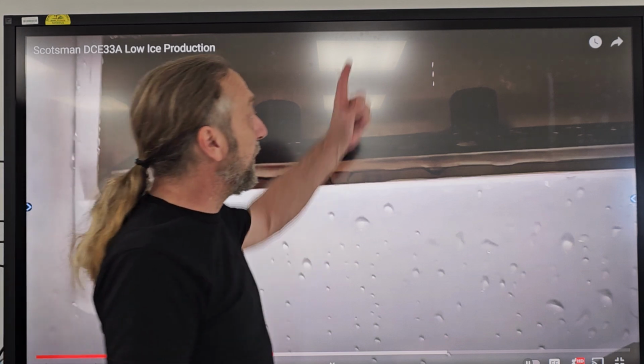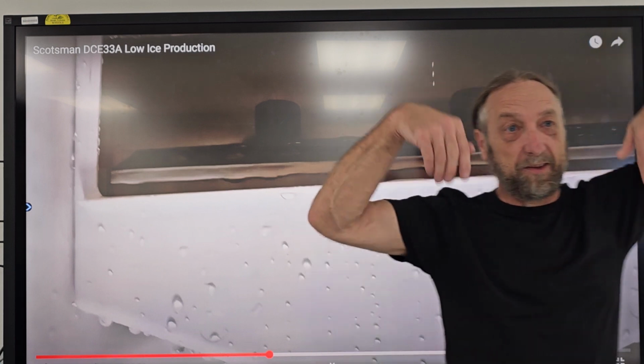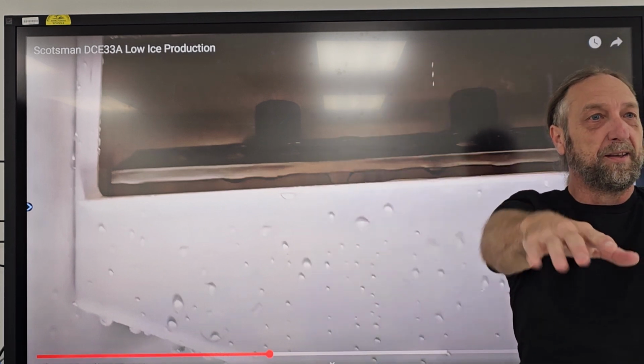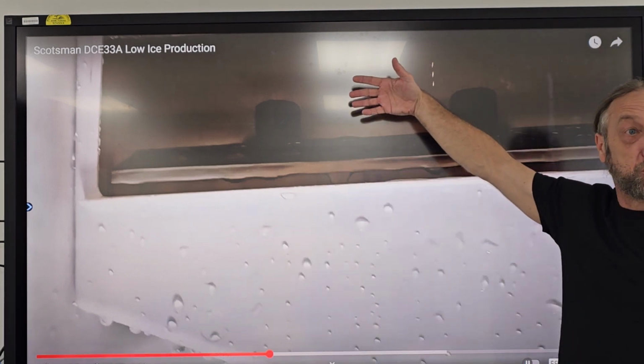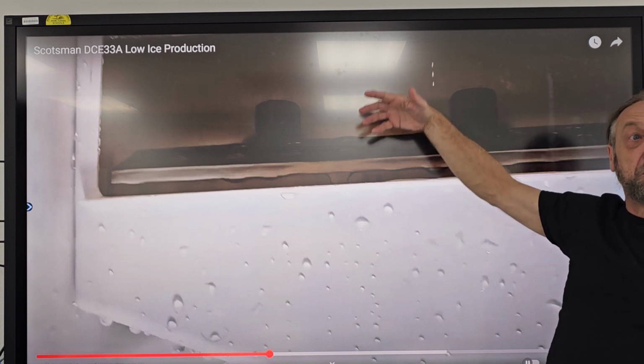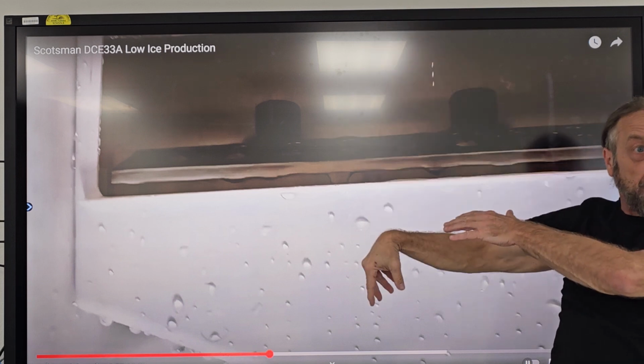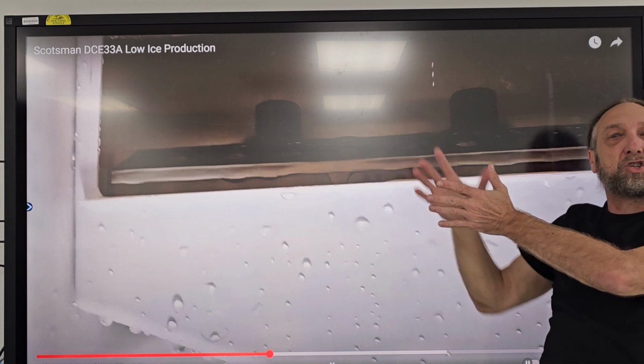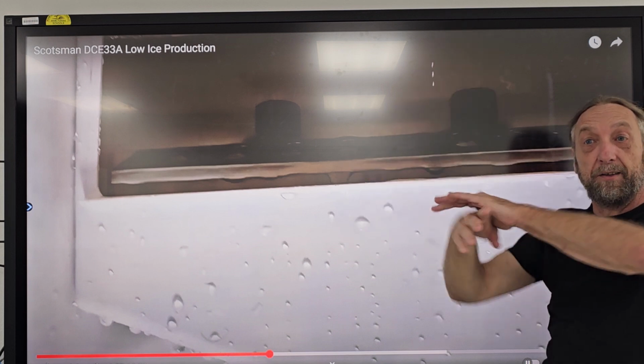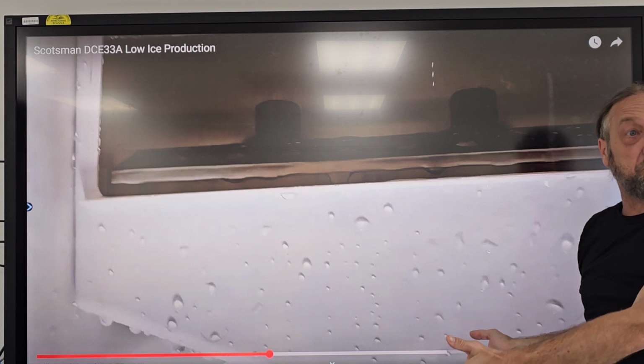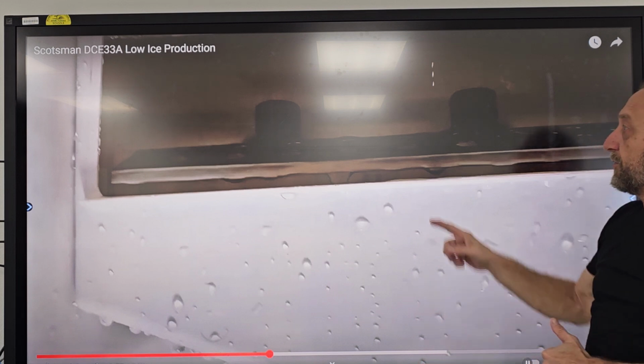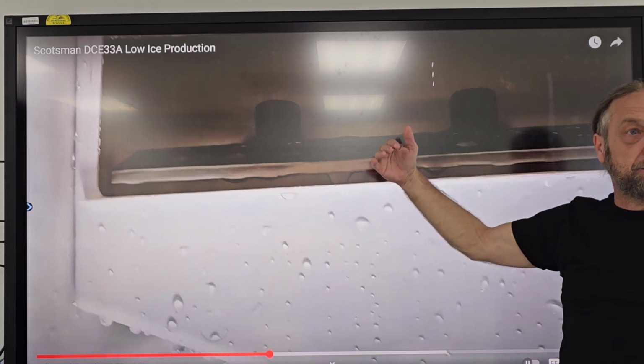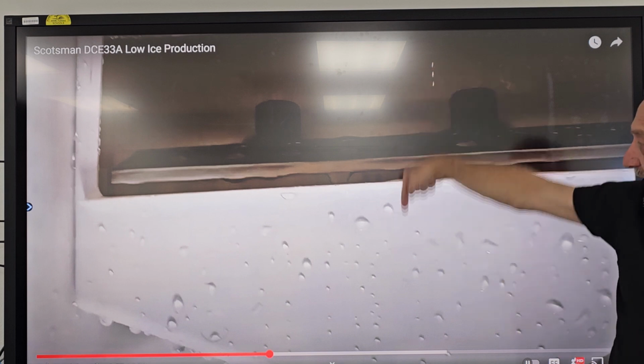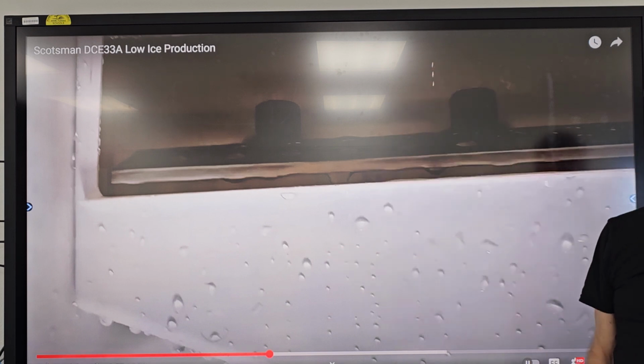When the ice falls out of the evaporator up there, it hits the metal plate and falls into the bin. That's why we have that plastic sheet - it keeps the water spraying up contained in the bin, but it's not so strong, so when the ice falls down, it can fall into the storage bin at the bottom. That metal plate guides the ice out and not back into the water; otherwise it would fall back in where the water is.